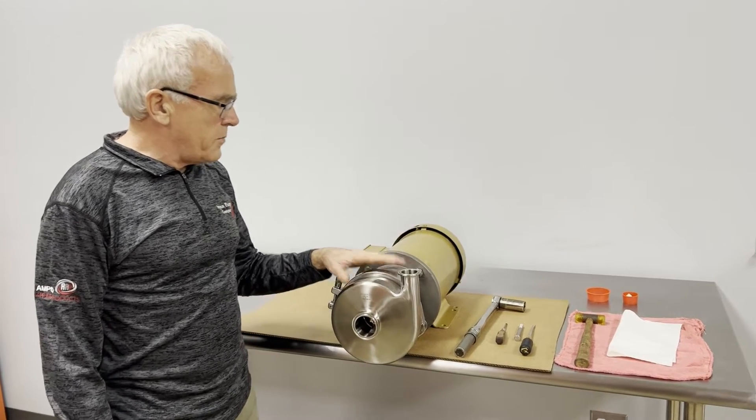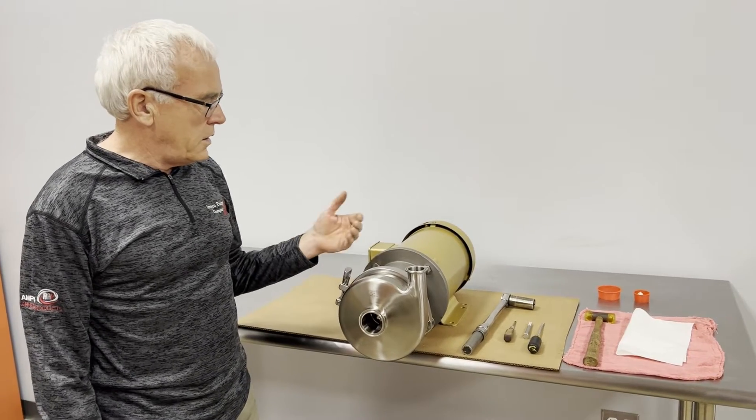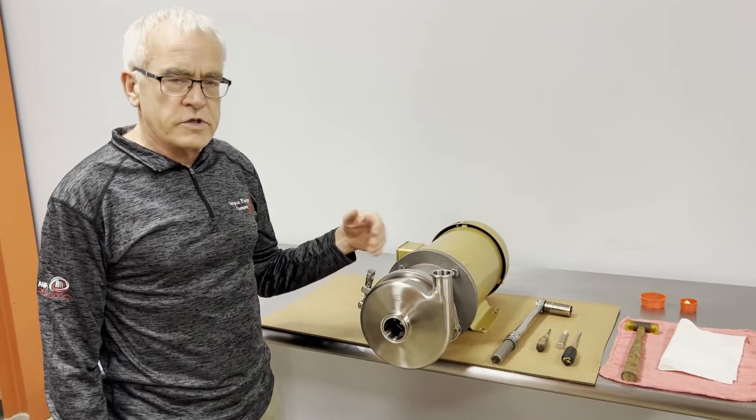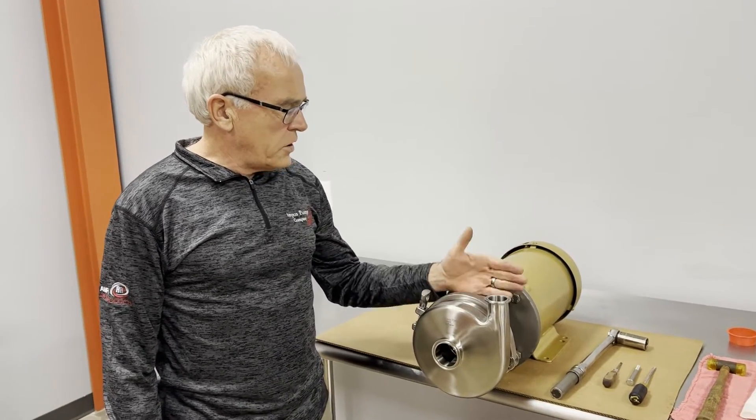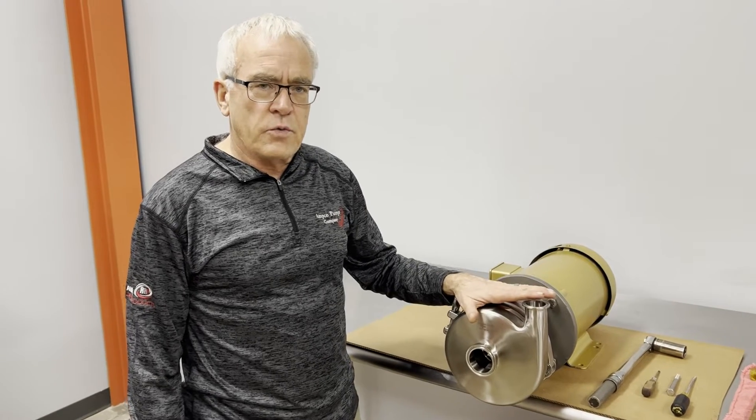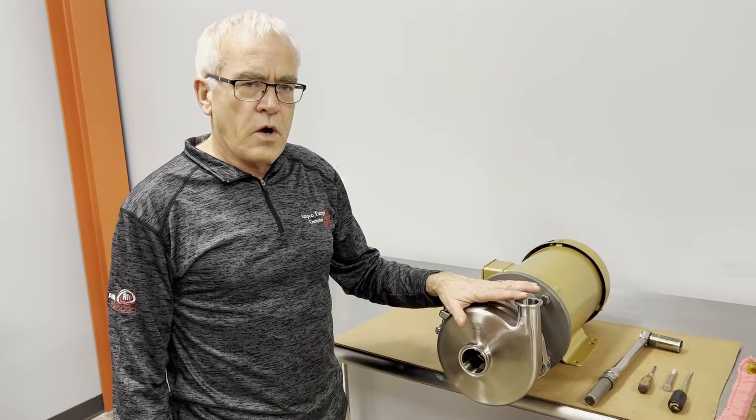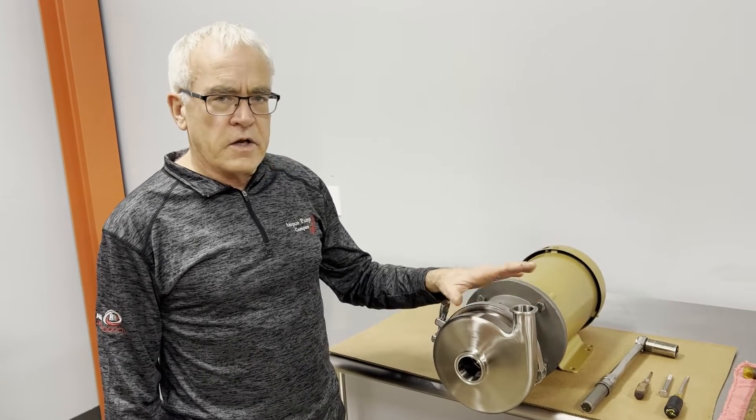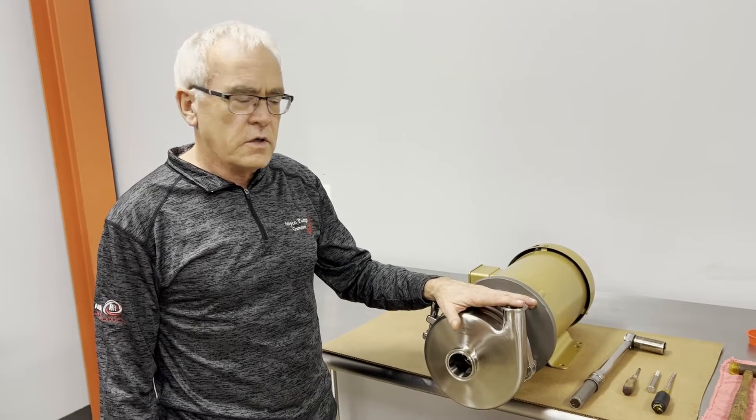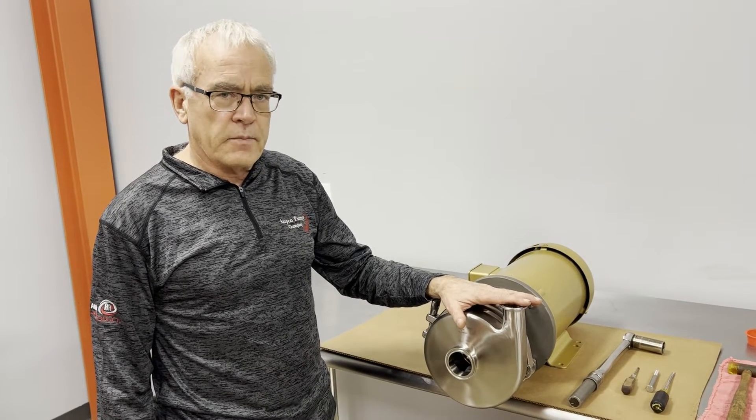A little history behind this pump: originally it started out as a food and dairy pump. We still sell a lot of them in the food and dairy industry, but that particular pump had an external seal which didn't tend to do very well when pumping hot wort. So we designed this pump with an internal seal that runs cooler than an external seal and does very well in the hot wort applications.